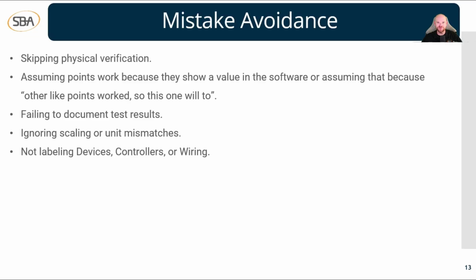I'm not going to beat up this one too bad. I think I've already hit this one pretty good, but documentation, guys, make sure you document. All right, fourth point is ignoring the scaling or unit mismatches. So if we have a temperature sensor, but we've got it set up for CO2, obviously it's not going to read right, and in our brain when we see it on the software, it's not going to make any sense. So make sure we're scaling our software configurations right, and make sure that our unit facets or their units of measurement match what the actual device is.